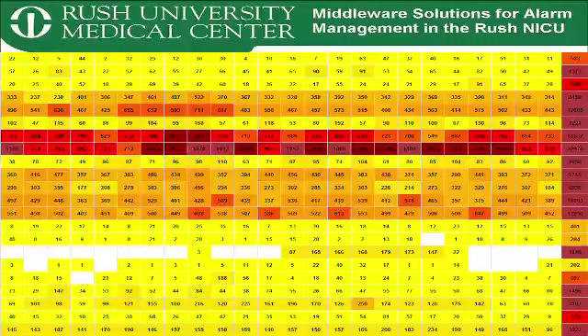And this is a Connexall report called a heat map, and I stripped off all of the patient identifiers and room numbers. But just to show you the variability, we had a set of twins that were desaturating almost nonstop during that time. It's hard to see the numbers, but this is 18,000 and 22,000 alarms just from those babies over a month, as opposed to other patients where, look, here's one with 200. So you go from 200 to 22,000, and you can imagine that alarm fatigue is, even though you can look at what your average is, there are individual patients who may be causing dramatic alarm fatigue, even though the average for your unit is not very high.